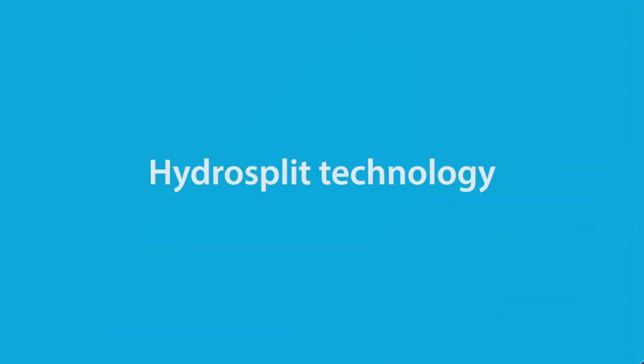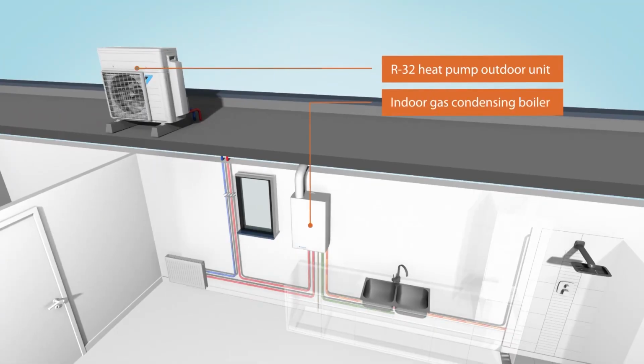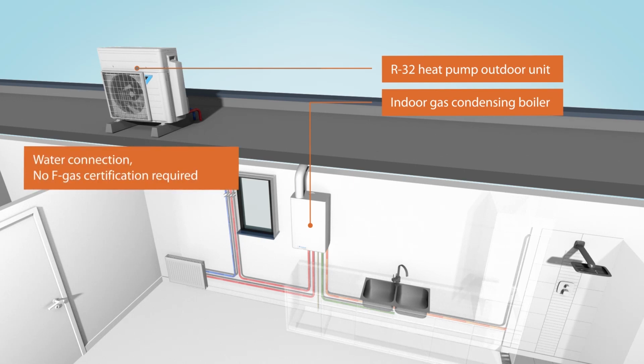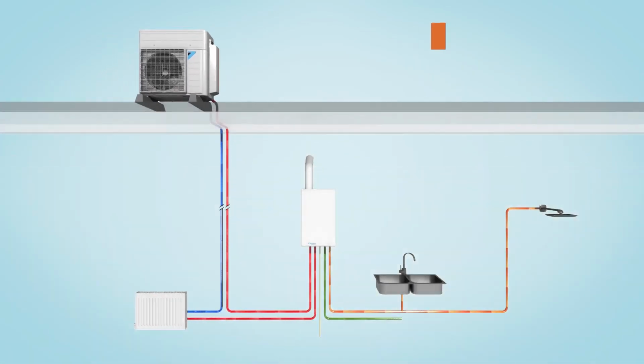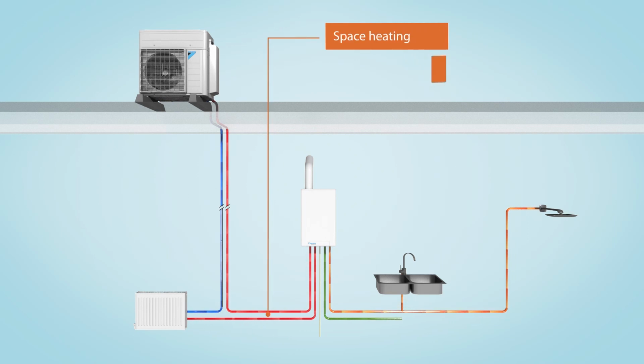The Daikin Altherma hybrid monobloc is a heat pump with a sealed refrigeration system. It uses hydrosplit technology, which means there are water connections from the outdoor unit to the indoor unit. For the installer, this means they do not need to be F-gas qualified. Installation is only a plumbing and gas-safe exercise. For the property owner, they can benefit from faster boiler replacement available from their usual heating engineer. The Daikin Altherma hybrid monobloc system's high efficiency is because it uses R32 refrigerant, which has a low global warming potential and a much better performance compared with any R410A based heat pump.